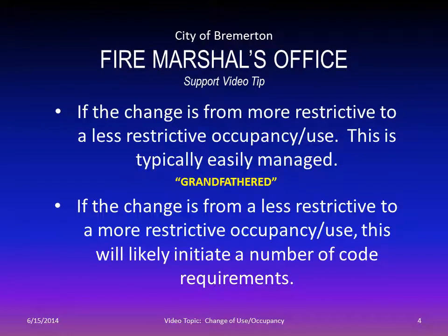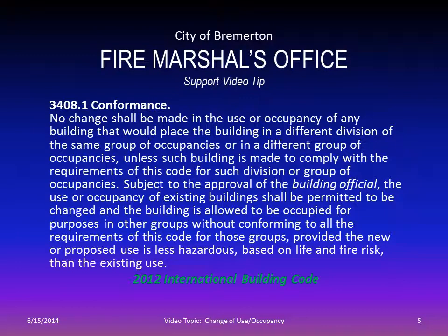If the change is in the form of less restrictive to more restrictive, that's when you're going to see some of the code requirements kick in. If you're going from an occupancy that has a lot of code requirements in it to something that's less restrictive, then you're going to be okay. That's going to be better. Some of those comparisons, though, are going to be, would a fire protection system be required? What about egress? So the number of doors, the hardware on those doors, push bars, panic bars, those types of things. If you're going from something that has been highly regulated to something that doesn't require as many code requirements, then you're going to be okay.